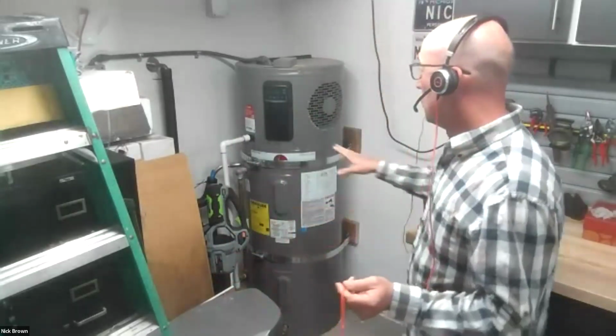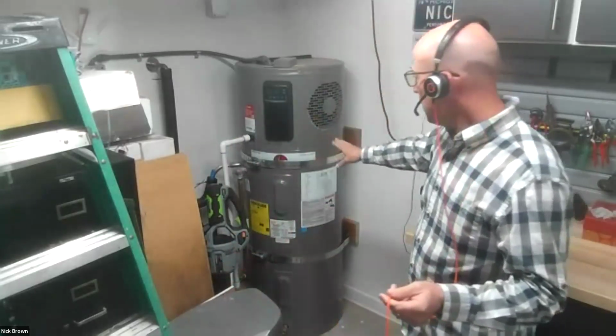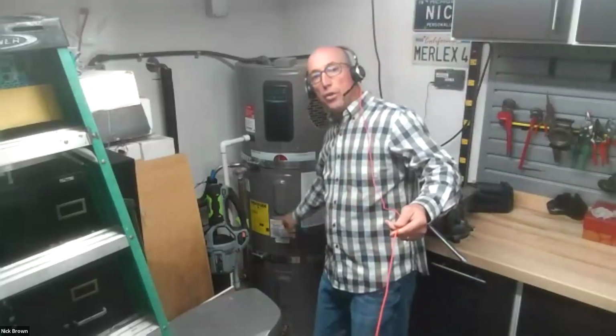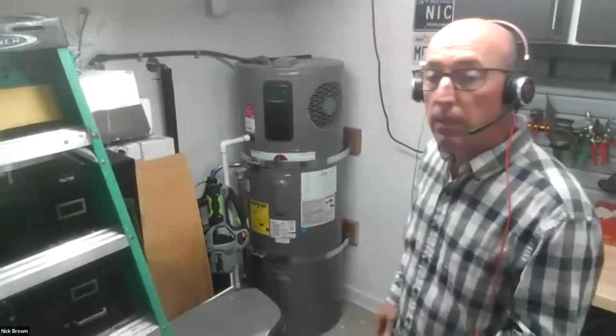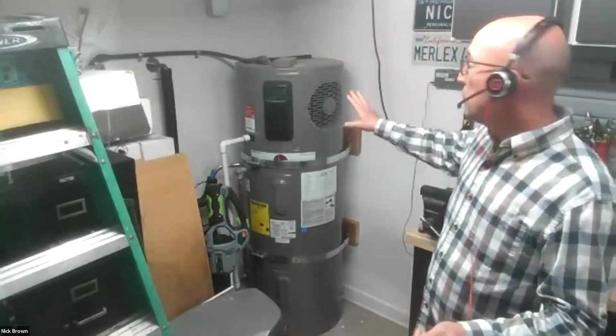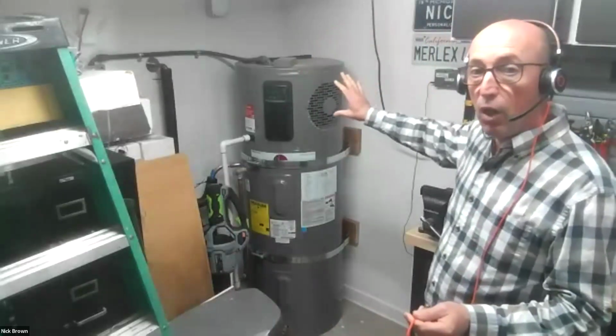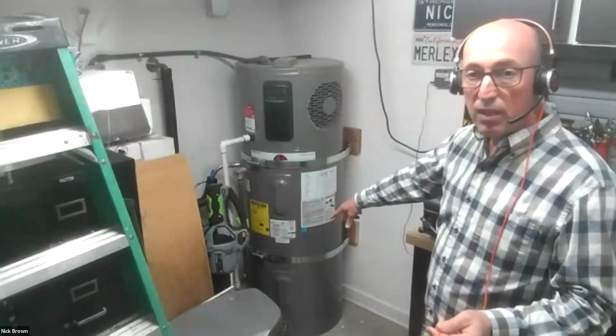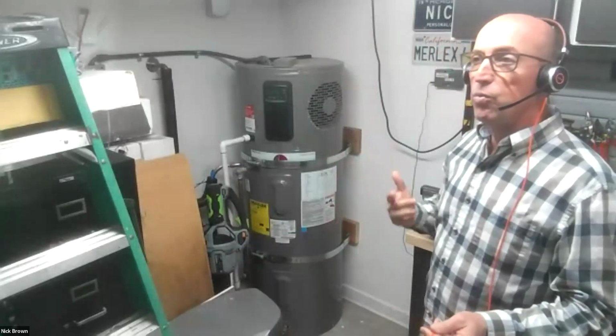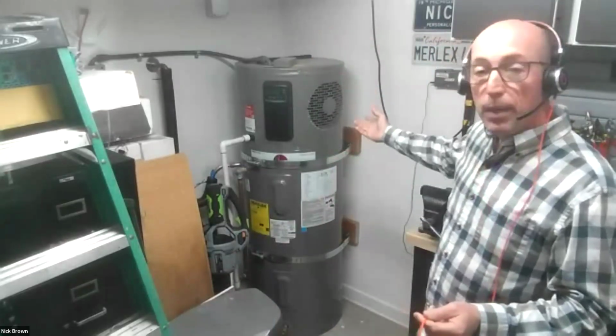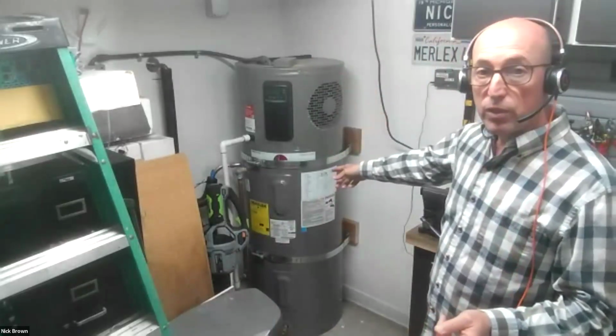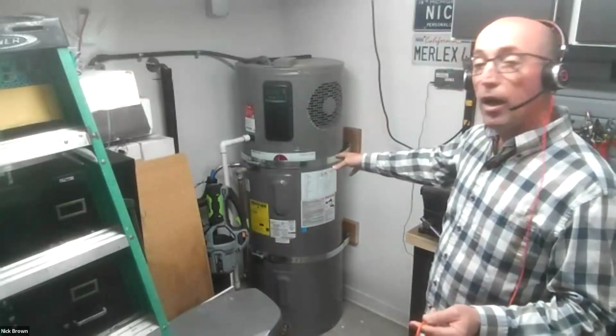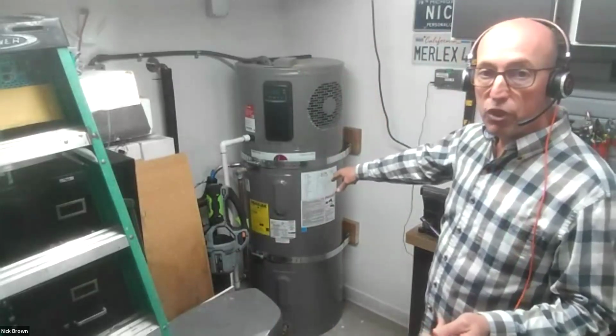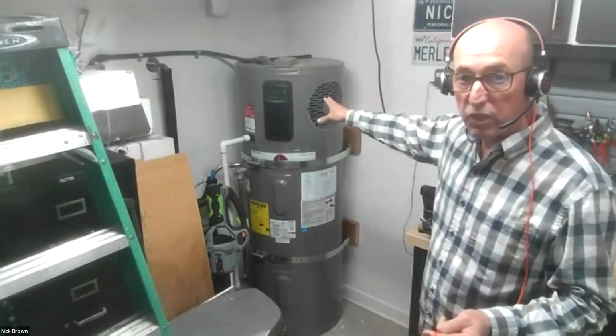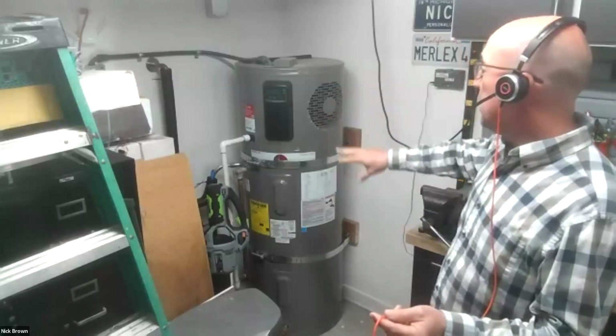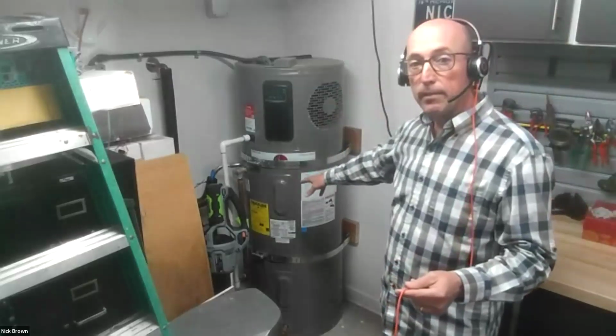It's important to note that this is one of the 240 volt units, and you'll see these bulges here and here - those are the electric resistance backup elements. Heat pump water heaters, you want them to run in heat pump mode as much as possible, if not all the time. But the electric resistance elements are there for backup on those really cold days when your heat pump can't keep up. Those elements kick on and do the job, but they're only 95% efficient, whereas the heat pump is 350% efficient. So these are designed to use electric resistance only as backup.